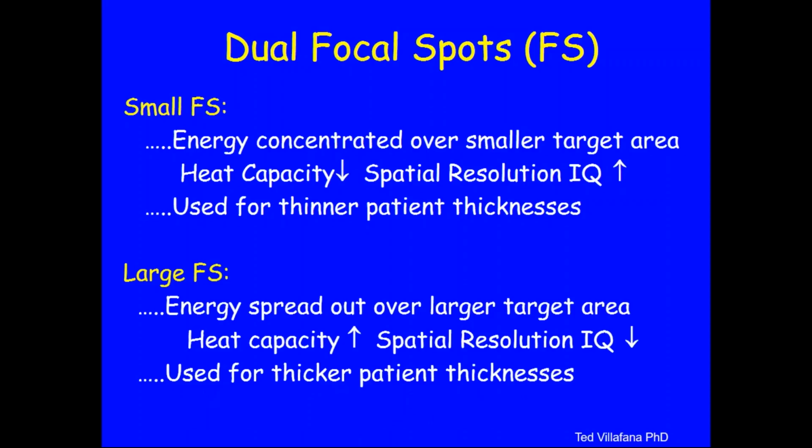on spatial resolution. Well, if spatial resolution is so good for small focal spots, why would we want to go to large focal spots? See, large focal spots will give us poorer resolution. Oh, that's bad. But if you have a large patient and thicker cross sections that you have to penetrate and denser regions of the patient that you have to penetrate, that means up goes the kV, up goes the mA, up goes the exposure times, and up goes the heat load.